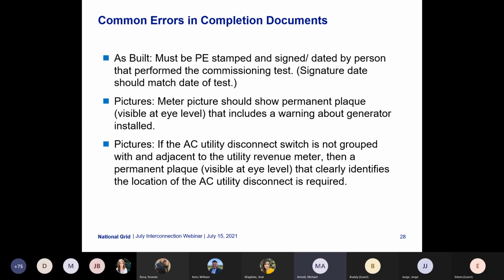Common errors that we also find in completion documents is, as I mentioned, it must be PE stamped and signed, dated by the person that performed the commissioning test. So the signatures and dates must match. Pictures. The meter picture should show the permanent plaque visible at eye level that includes a warning about the generator installed. We should also have a picture of the AC utility disconnect switch. If it's not grouped with and adjacent to the utility revenue meter, then a permanent plaque visible at eye level that clearly identifies the location of the AC utility disconnect is required.